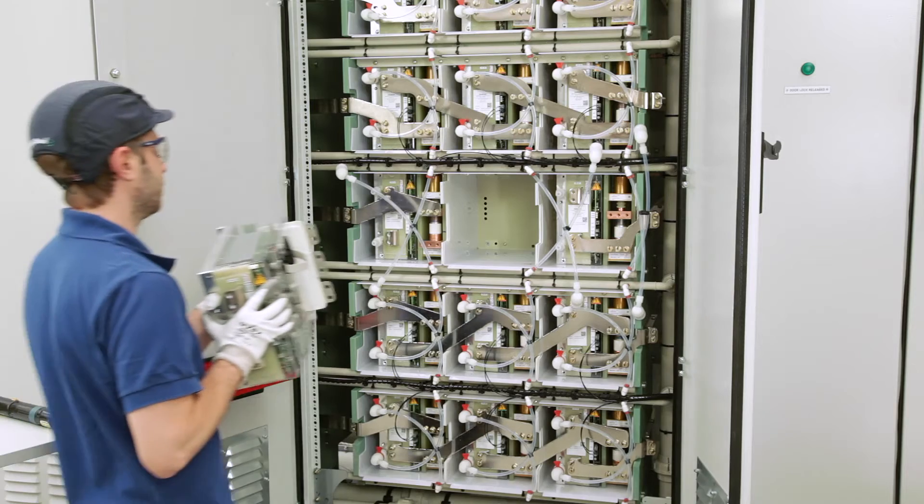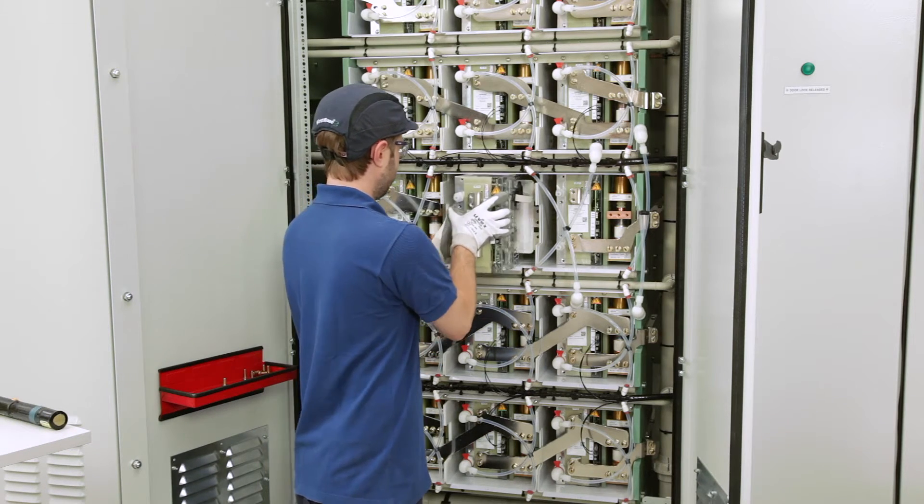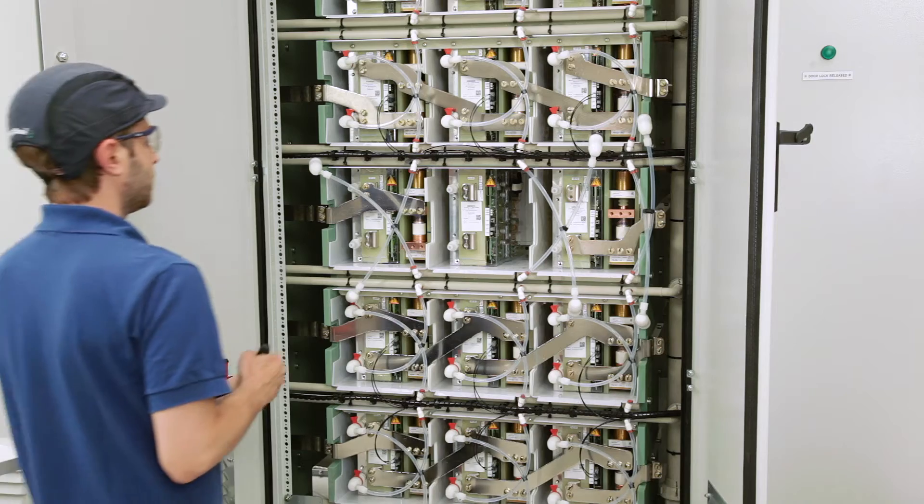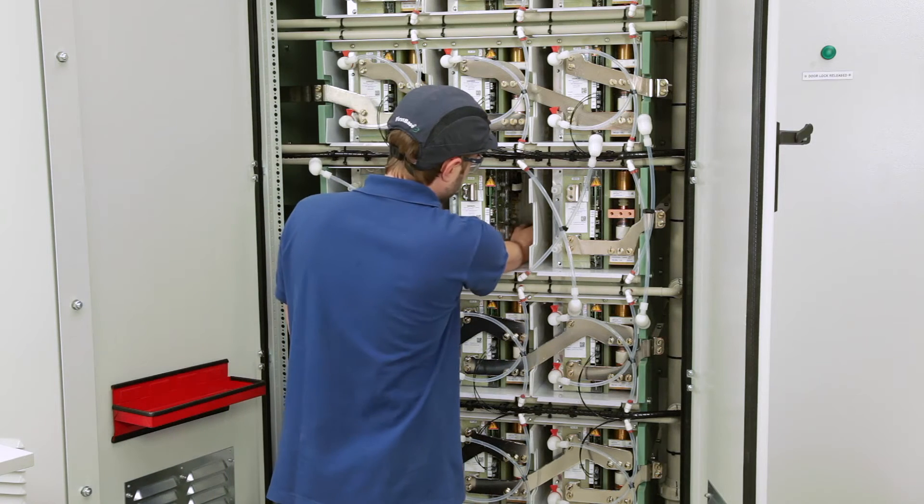Now you can push in the new IGBT module. Next, tighten all screws between the IGBT module and the capacitor bus bar. Make sure that all screws have been tightened with the correct torque.